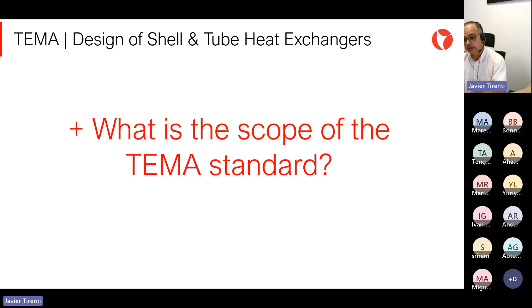In terms of scope and limitations, what type of equipment can be designed under this code? In terms of diameter, the limit TEMA sets is 100 inches. The inside diameter of the shell and tube heat exchanger needs to be under 100 inches, or 2,540 millimeters. In terms of pressure, it needs to be under 3,000 psi, or 210 bars. There's also a limitation on the product of pressure and inside diameter, which is a consequence of the two limits above.